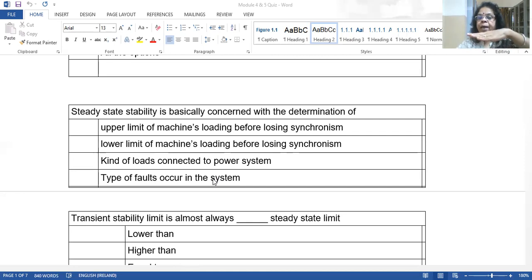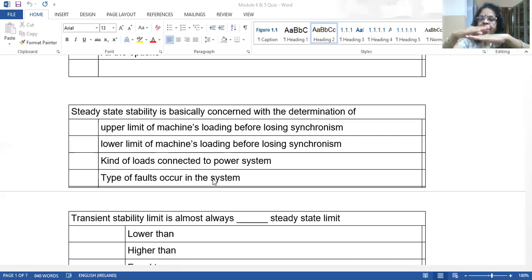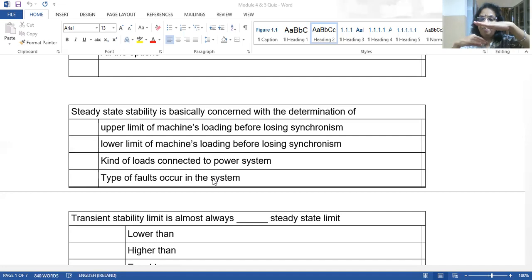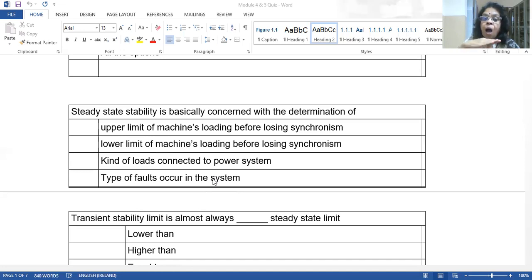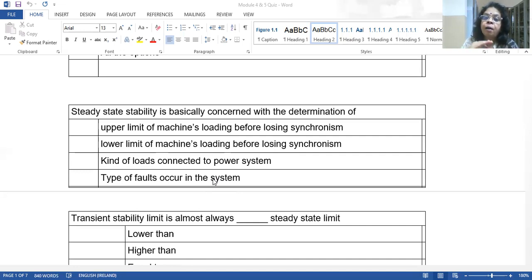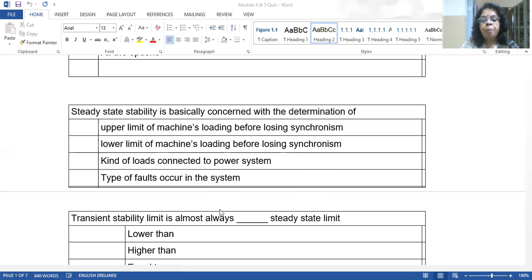Steady state stability is basically concerned with the determination of the upper limit of machine loading before losing synchronism. If the system is in steady state and normal variations occur, what is the maximum power transferable while maintaining stability? That is the steady state limit. Operating at some power level P1 with fluctuations, the system oscillates and returns. As loading increases to some limit, any further increase makes the system unstable. Therefore, steady state stability determines the upper limit of machine loading before losing synchronism — not the lower limit.